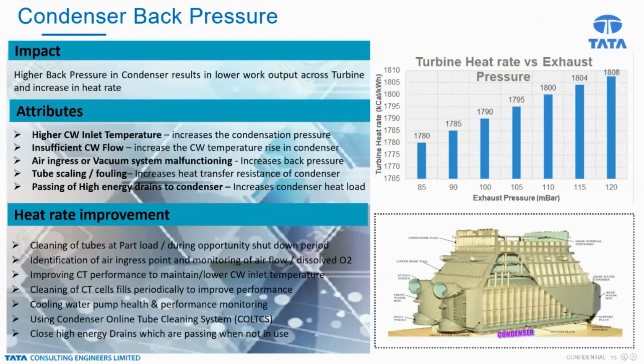We all know that in the condenser, it is very essential to maintain the vacuum and there should not be any ingress of air. Proper sealing is very important. So in case there is any air ingress or vacuum system malfunction, then this will also increase the condenser back pressure and in turn this will increase the turbine cycle heat rate. The scaling and fouling in the condenser will also affect the heat transfer surfaces and create a resistance in the heat exchange, and that will also increase the back pressure of the condenser.